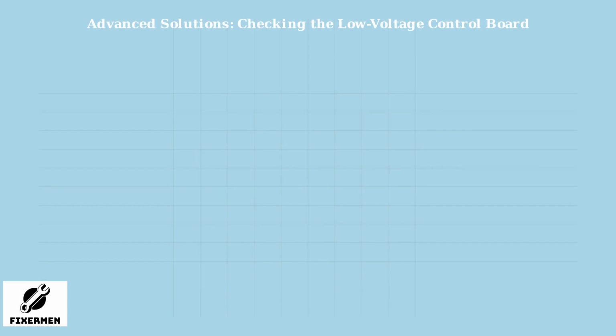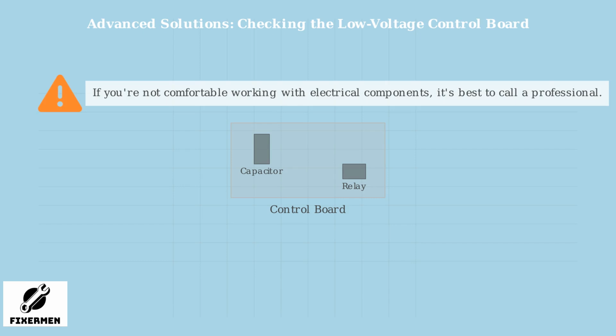If the basic steps don't work, the problem might lie in the low voltage control board. This component manages the electrical signals that control your AC unit's functions. The low-voltage control board contains components like capacitors and relays that can fail due to discharge issues or malfunctions. Capacitors can discharge improperly, preventing the board from maintaining proper voltage levels and causing reset failures. Relays can stick or fail to switch electrical circuits, blocking the reset signal from reaching other components. While diagnosing these issues can be complex, cleaning the board with compressed air and ensuring proper connections can sometimes resolve the problem. If you're not comfortable working with electrical components, it's best to call a professional to avoid safety risks and further damage.